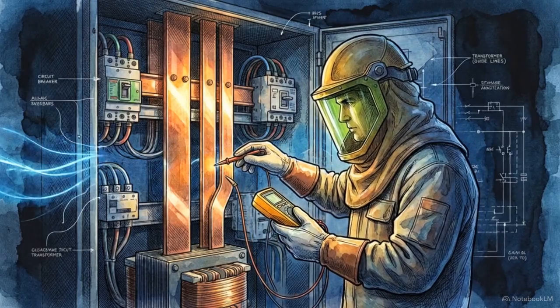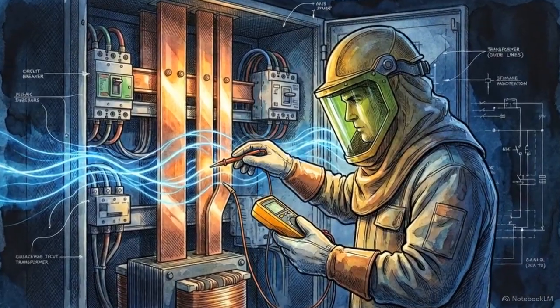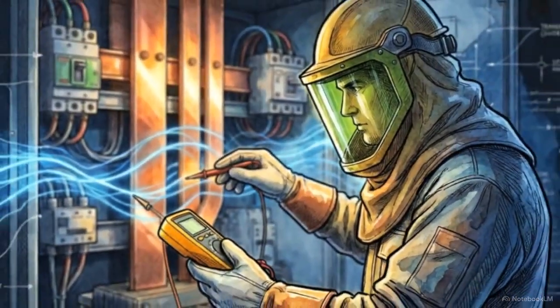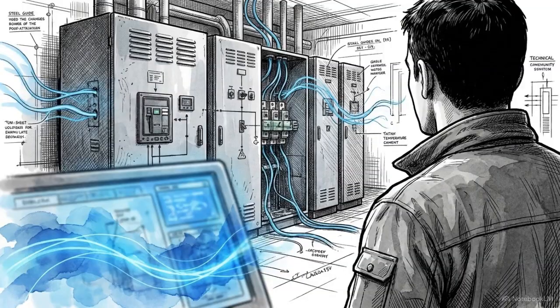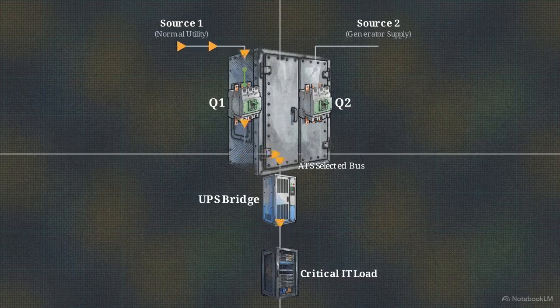You must verify the actual physical states, the mechanical breaker positions, the true source voltage, and the UPS battery readiness. You do not rely solely on the digital panel indicators. Every button press on the controller must have a specific, anticipated electrical result. If you command a transfer, you must know exactly what physical actions the switchgear is about to take. The digital screen provides a map, but the physical switchgear is the territory. By confirming the mechanical reality of the system, the operator serves as the ultimate safety interlock, keeping the powertrain online.